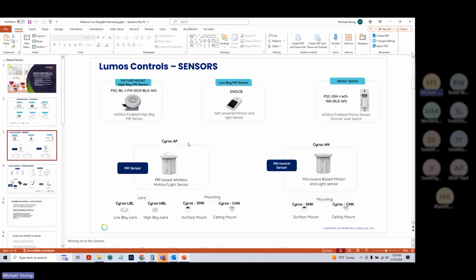And here we have the lighting sensors. All of the sensors, except for these two. This is both, I guess. I take that back. This is the only sensor that is just simply an occupancy sensor, and this is mostly for high bays. It's side mount, it has the case, or center mount, depending on how you want to go about it. But for every other sensor, and that's these three sensors here, they are motion and light sensing devices. This is where the magic happens in our daylight sensing technology.